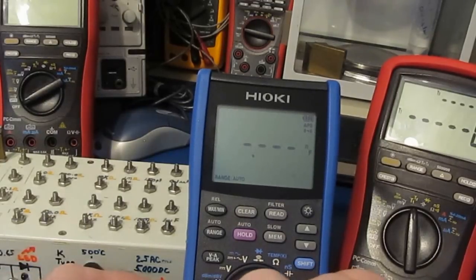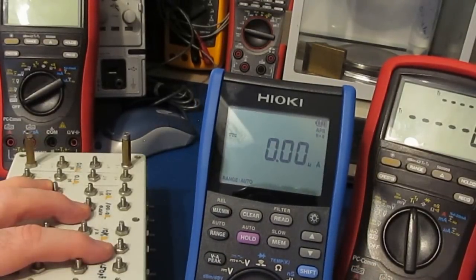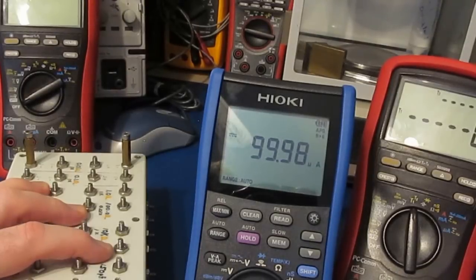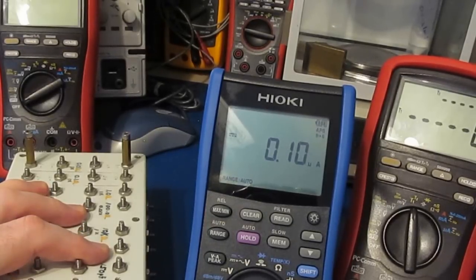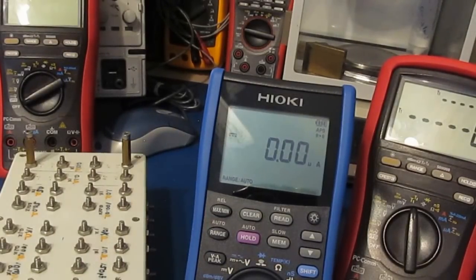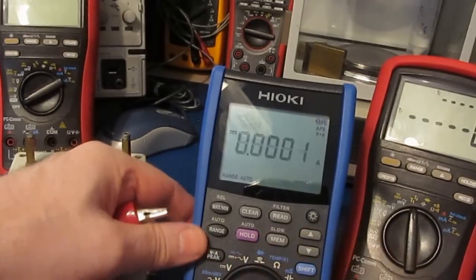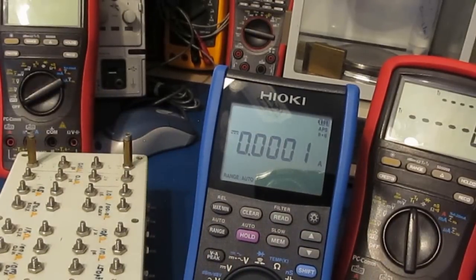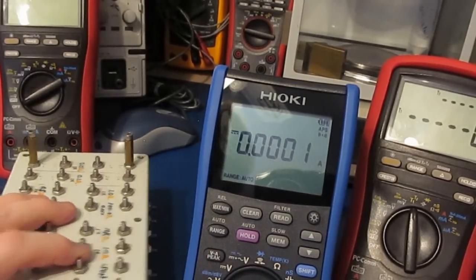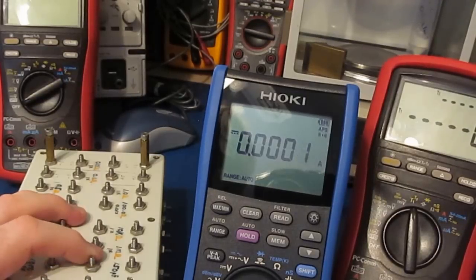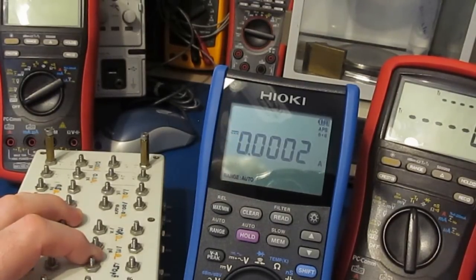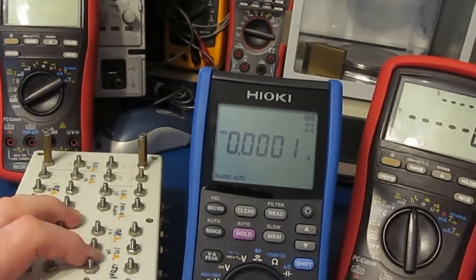Let's just try current real fast. This should be 100 microamps. And you can see that's spot on. This will be 10 microamps. That looks spot on. Here's 1 microamp. That looks good. And 100 nanoamps. That looks good. I guess we can try the high current mode real quick. Crank this thing all the way up. Again, this will be 100 microamps. Does it flip a count? And it looks like it does flip a count, so at least the fuse in this meter is okay.